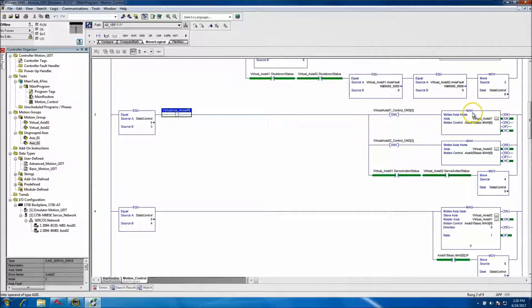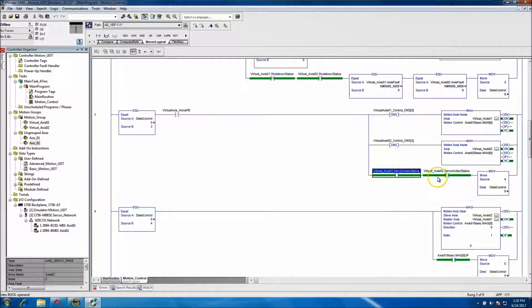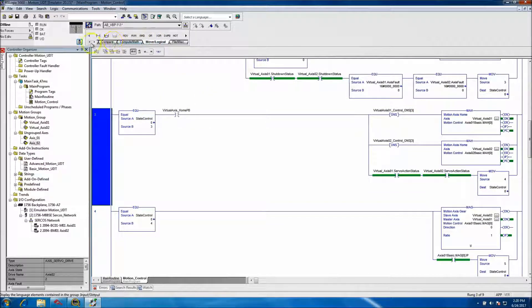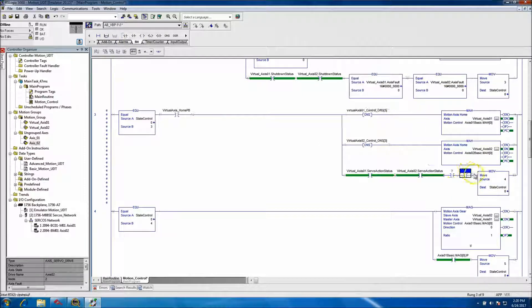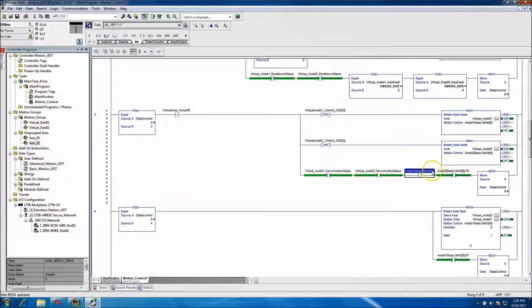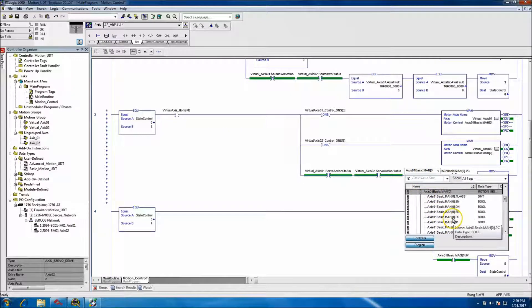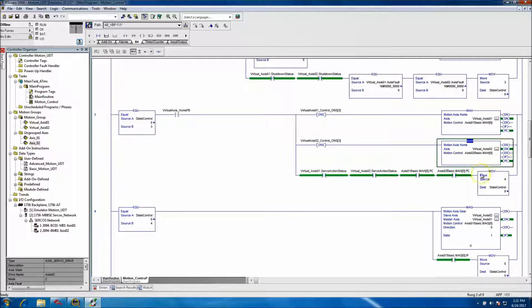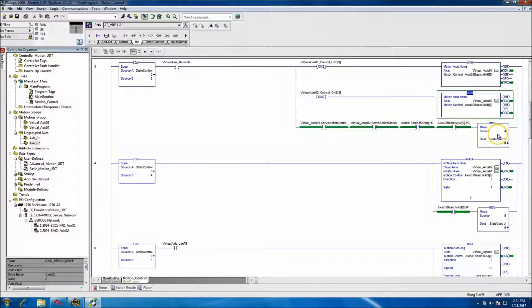When we home the axes they go to zero. We're not looking for a home status; we're looking for the action status to come on. We can also verify the PC bit came on. You want to use the PC (Process Complete) bit, not the IP (In Process) bit. Those are what those abbreviations mean. You use the IP or PC bit when transitioning states, not the error, enabled, or done bits.